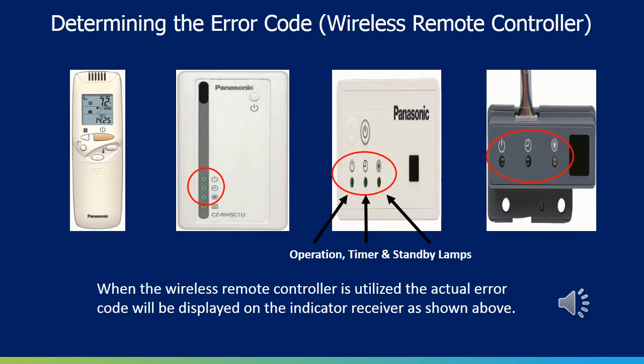The indicator receiver lamp assembly receives the command from the remote controller and sends this command to the indoor unit's control board. There are 3 lamps used for the error code diagnostics: the green operation lamp, the amber timer lamp, and the red standby lamp. The error code is displayed by the sequence of these lamps, not the actual continuous number of blinks. These receiver assembly lamps can do one of 3 things: stay on solid, blink, or stay completely off. Based on the sequencing of these lamps, the error code can then be determined by referencing the error code listing found within the Service Technical Manual.